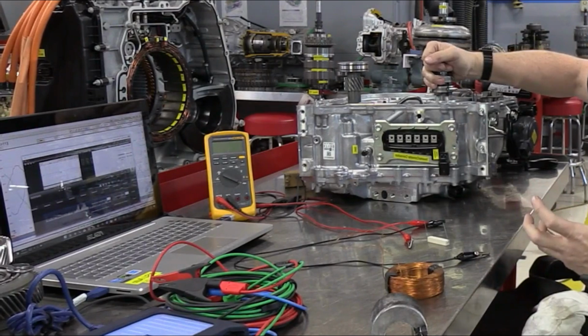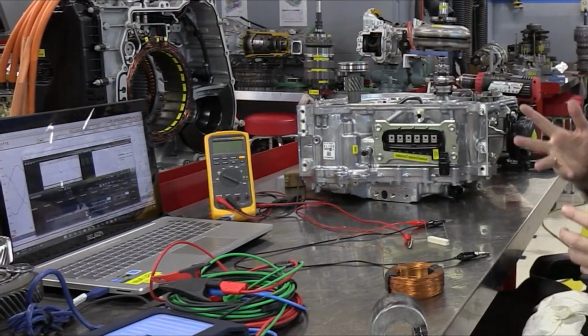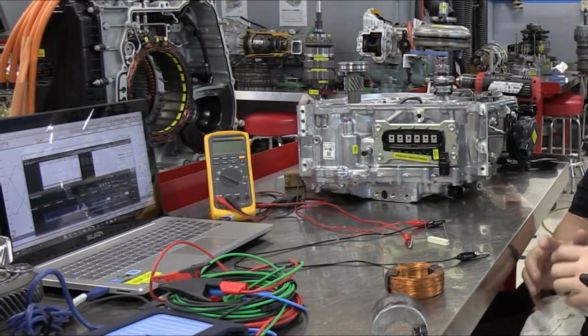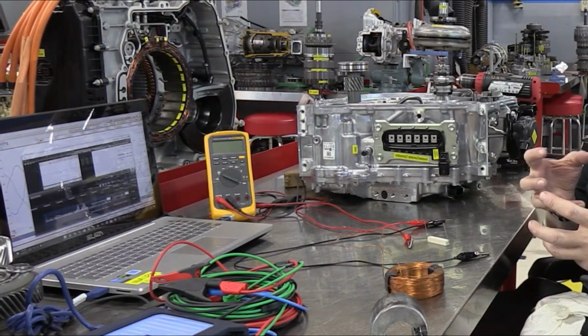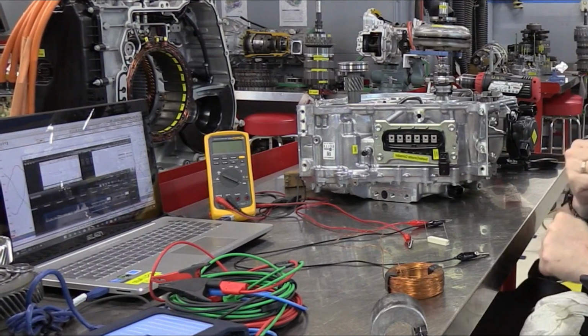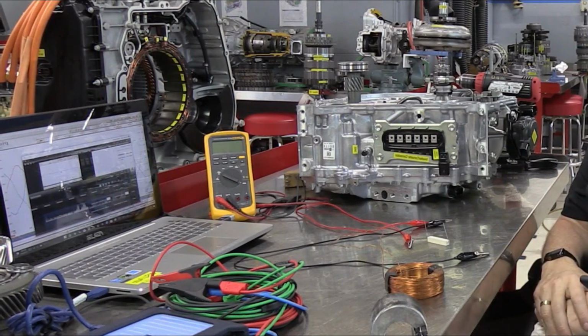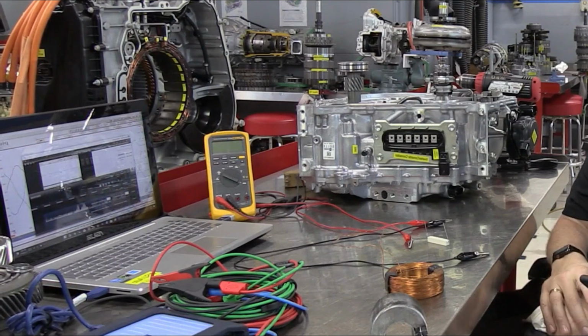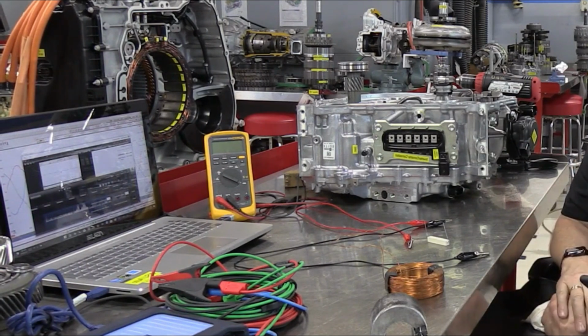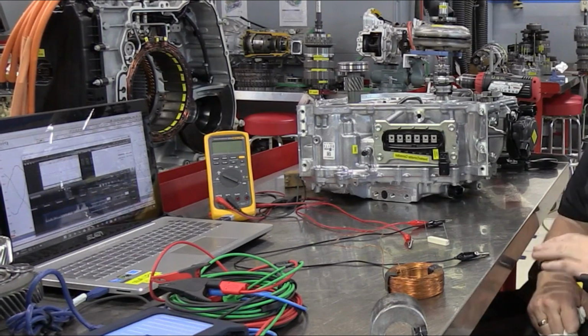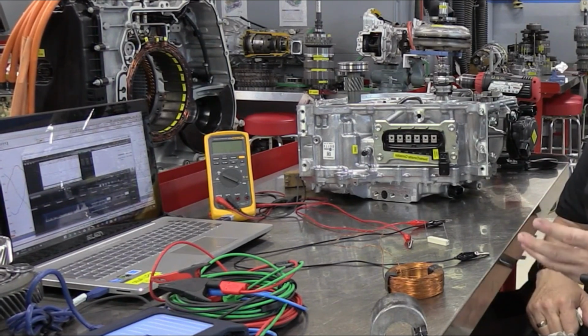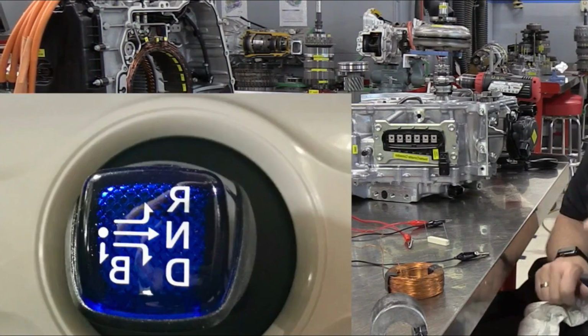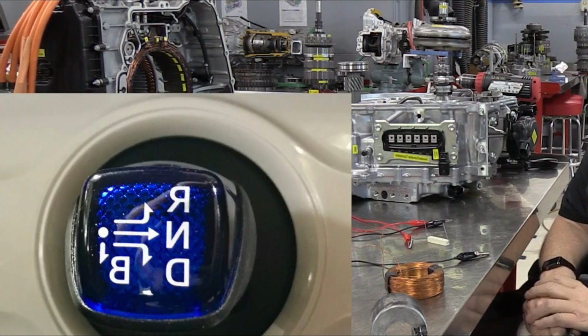Initial diagnosis included motor current signature analysis, which revealed irregularities in the stator current waveform, a specific harmonic often related to an inter-turn short circuit, which was amplified. In further investigation, engineers performed partial discharge testing to identify insulation weakness in the stator winding. The test indicated a localized breakdown in insulation, confirming an inter-turn short circuit. Thermal imaging showed hot spots in the winding, reinforcing the presence of a short circuit.